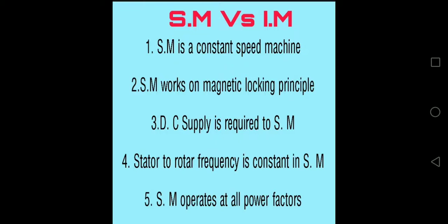But an induction machine operates at only one power factor, that is the lagging power factor. An induction machine is similar to an inductor. It draws the reactive power. A capacitor delivers the reactive power. So the induction machine power factor is very low.